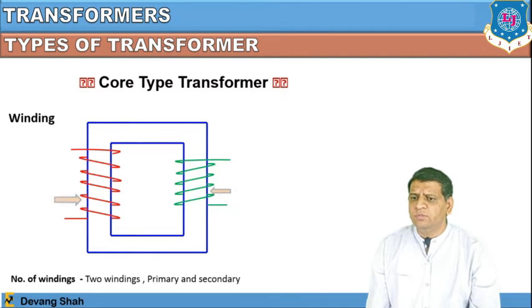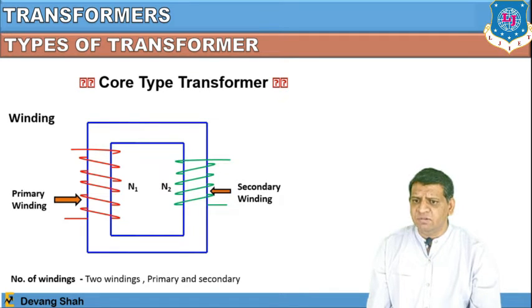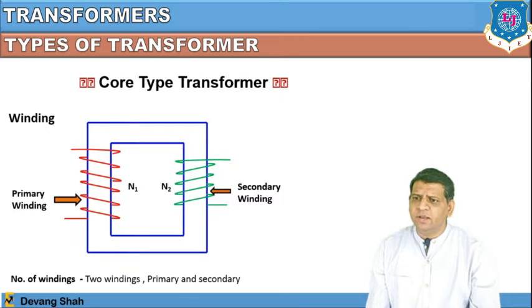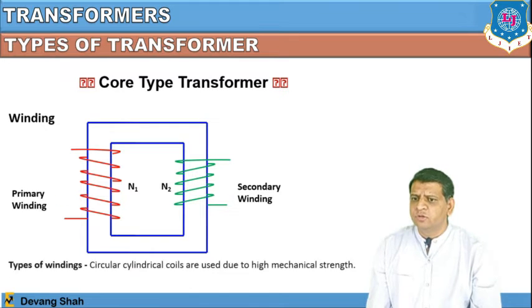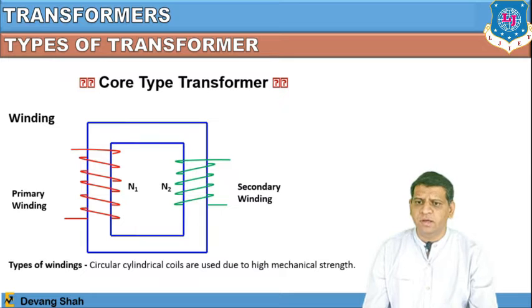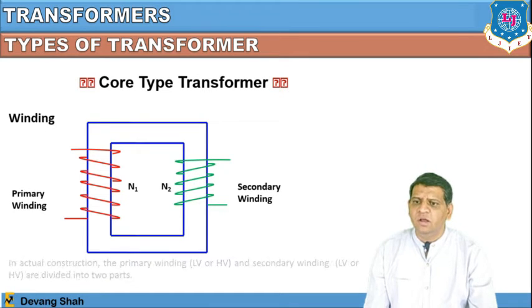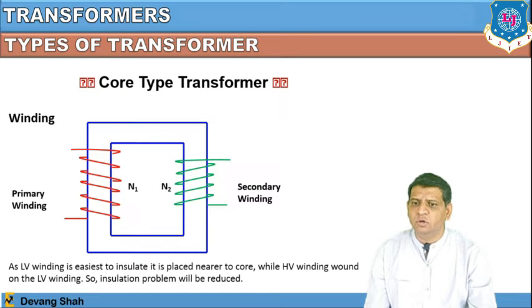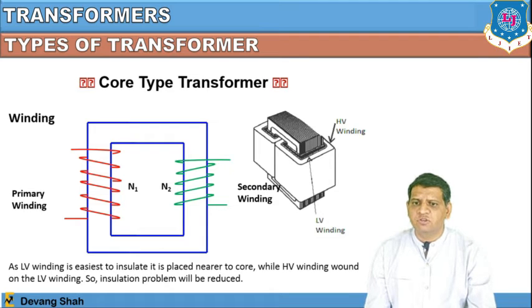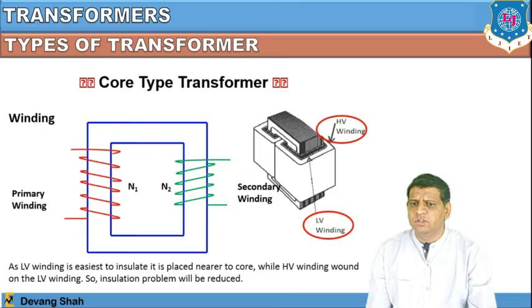Now let us discuss the winding of the core type transformer. There are two windings: a primary winding with N1 turns and a secondary winding with N2 turns. The winding shape is a circular cylindrical coil for high mechanical strength. In actual construction, the low voltage winding is easiest to insulate and is placed near the core, while the high voltage winding is wound on top of the low voltage winding to reduce insulation problems. You can see this in the core type transformer figure where two cylindrical windings are placed over the two limbs.